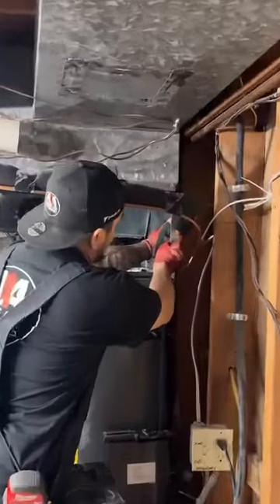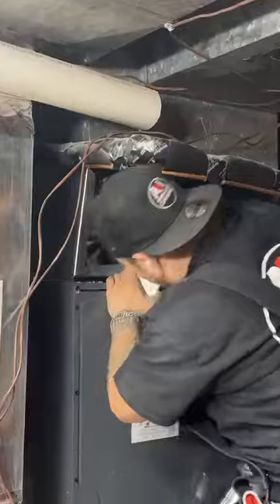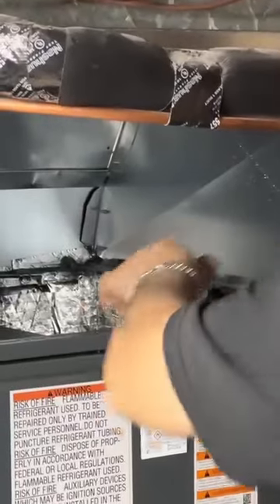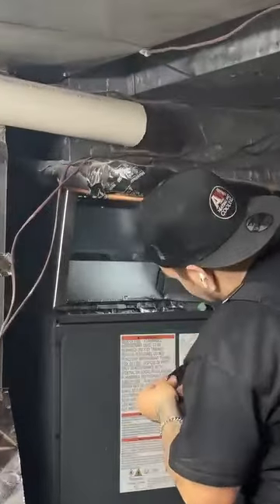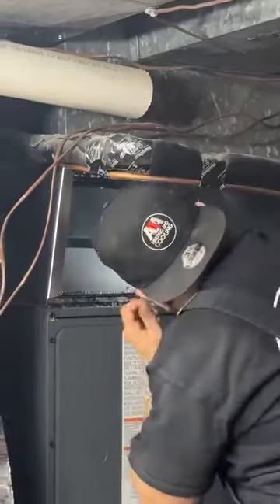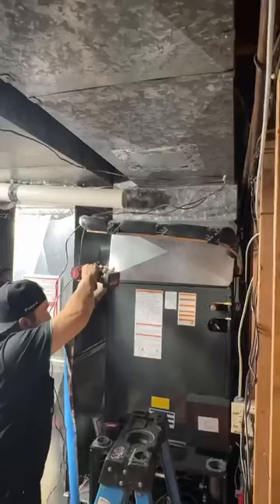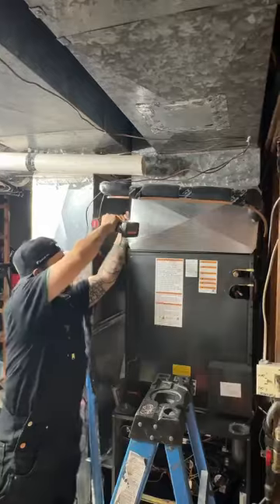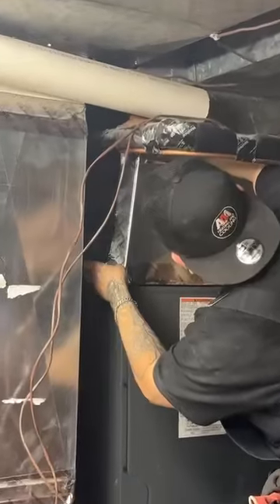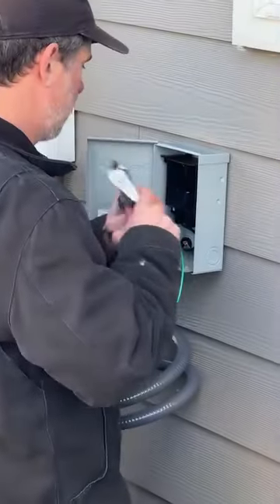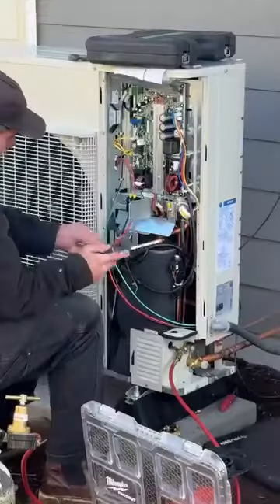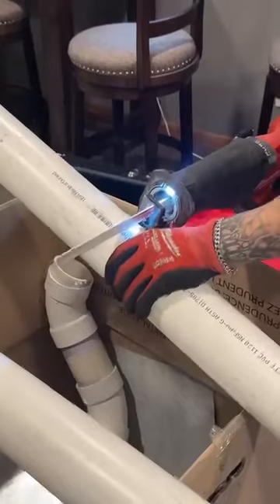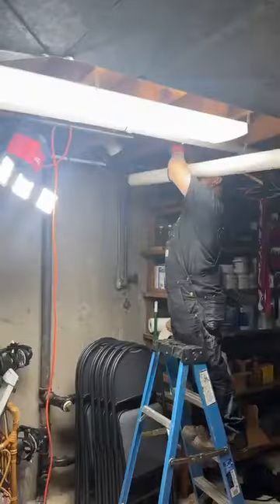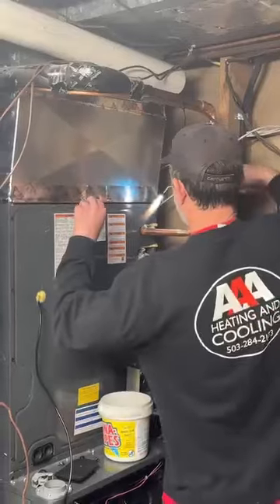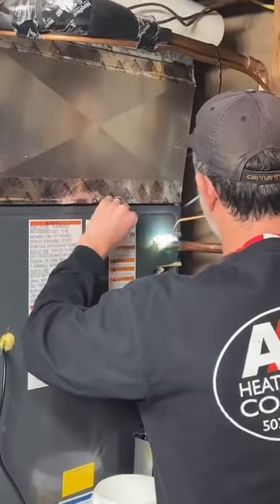Now we can begin installing the transition ductwork section. We also add that same metal tape inside the ductwork to prevent any air leaks as well during this step. Then we finish by securing the final front plate to the ductwork and applying that same tape to the outside as well. Meanwhile, outside we install a new disconnect box for the system. Next, we head back inside to build the new exhaust piping for the indoor unit. Then we begin the brazing process on the interior lines, which allow the flow of refrigerant through the new system.